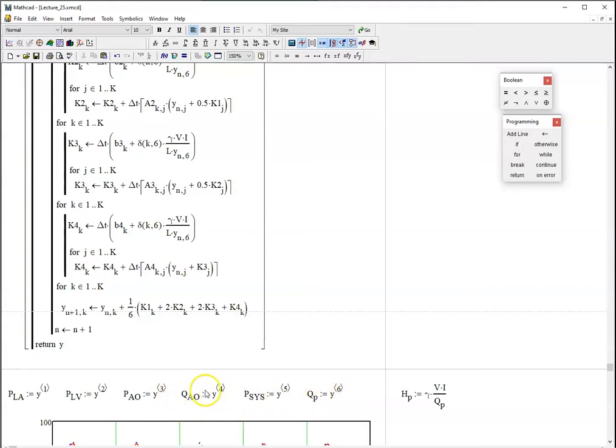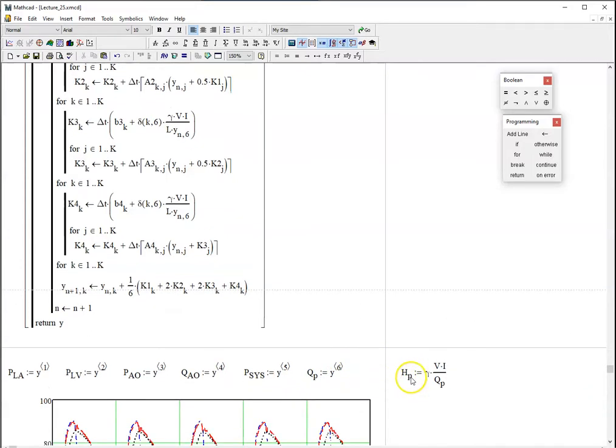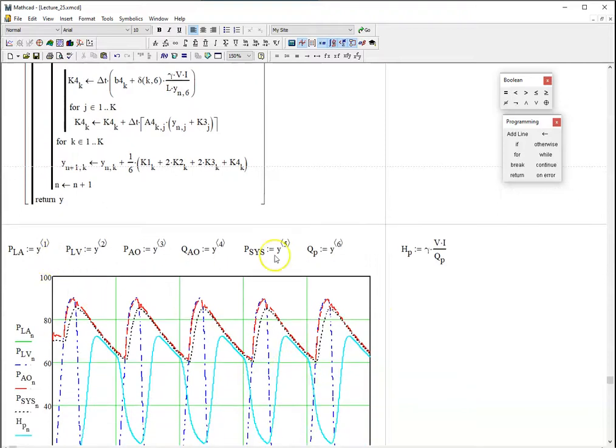The sixth column is the pump flow. Remember that the aortic flow contains both the pump flow and the heart ejection, or the cardiac output. In addition, we can calculate the head gain in millimeters of mercury within the LVAD as gamma times VI divided by QP. So now that we know QP, we can calculate another array, HP, and plot it along with the other pressures.